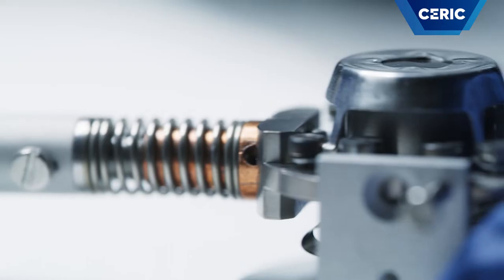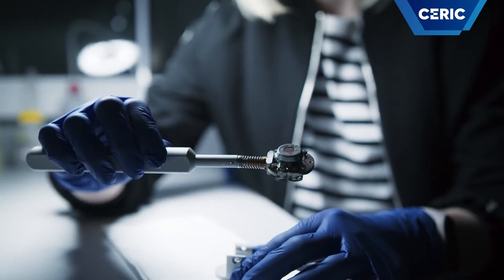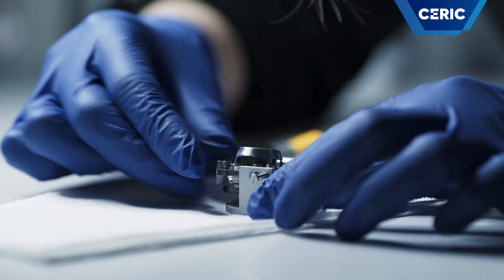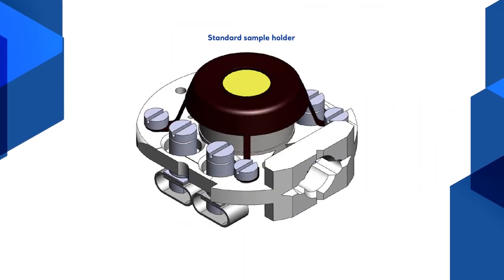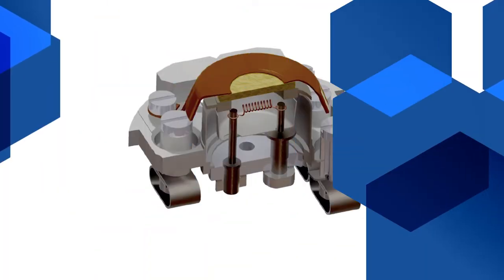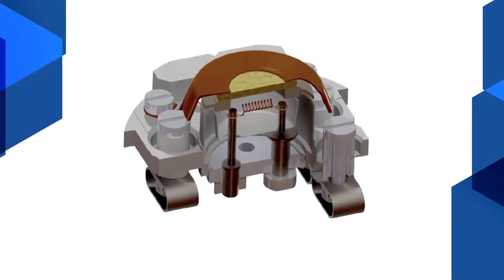Samples for the PEEM microscope have to be flat, conducting and UHV compatible. Typical size is around 10 mm in diameter. There are two types of sample holders: standard sample holders have a thermocouple and high voltage and allow high temperature measurements, while sample holders with an adapter for printed circuit board plates are used for current pulses.